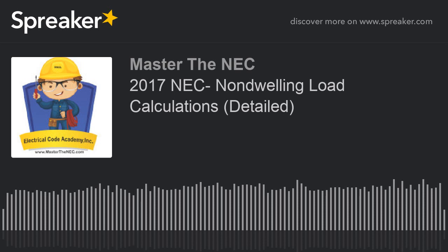So that's my next step. That's step 7. And I'm going to write that down. And that is going to be 6,000 VA. And I'm going to put a little asterisk beside that because if it's a store, then that is going to be on for 3 hours or more. It's a continuous load. I need to take that into consideration. Okay, so I write that down. And that's where I put that little asterisk there.